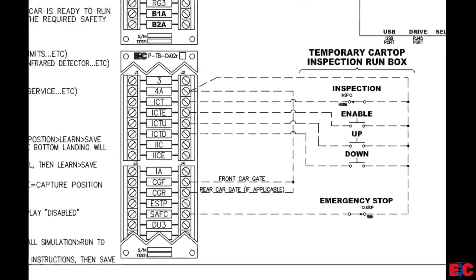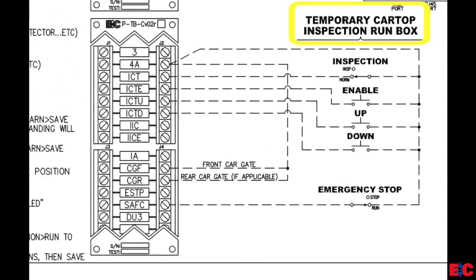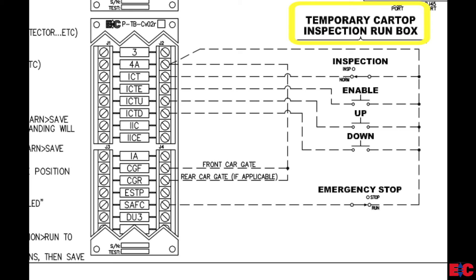And on the car top terminal board, we want to wire the stop switch from 4A to SAFC, the inspection switch from 4A to ICT, and the enable up and down buttons from 4A to ICTE, ICTU, and ICTD. Then wire your car gate from 4A to CGF and CGR if you have a rear car gate.